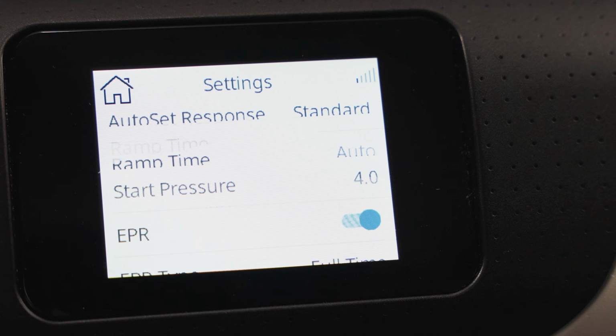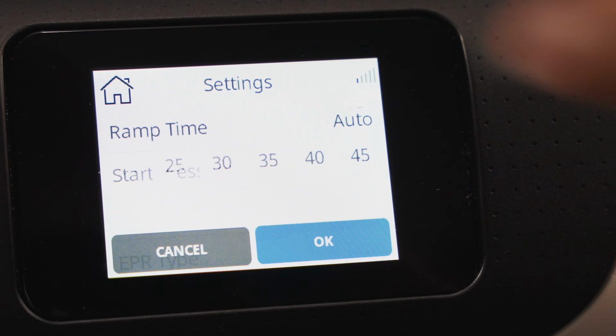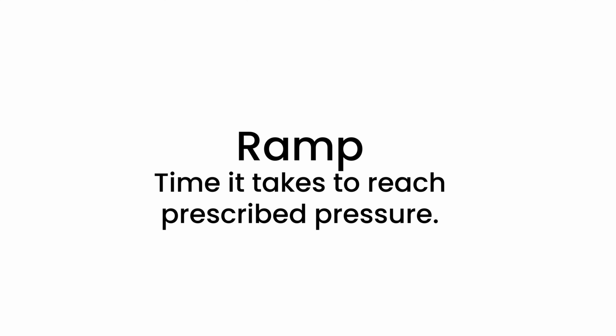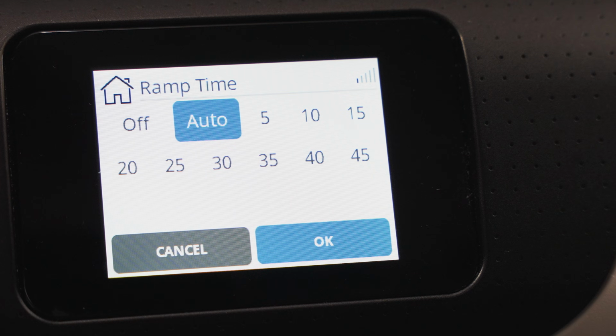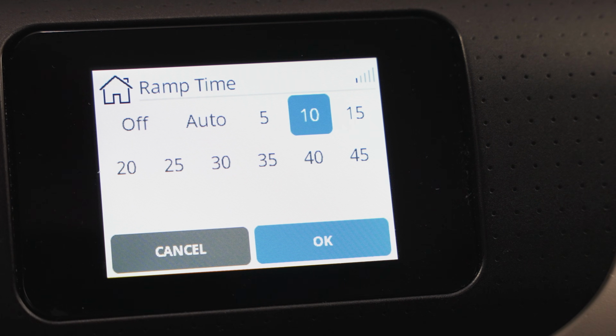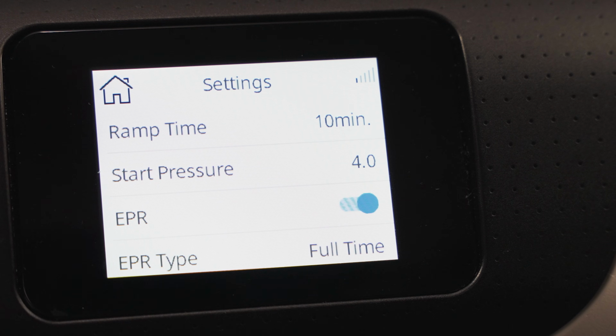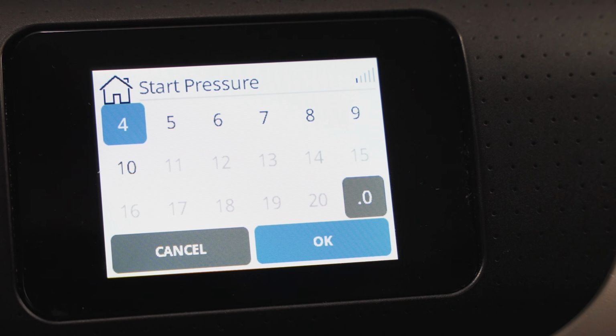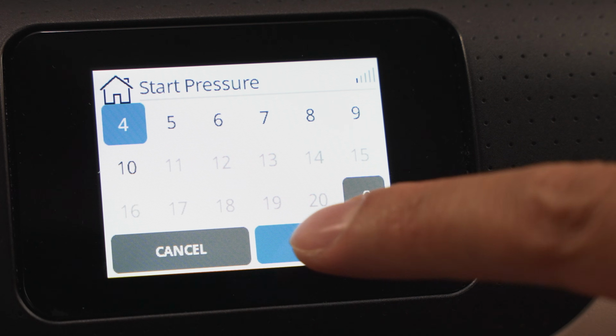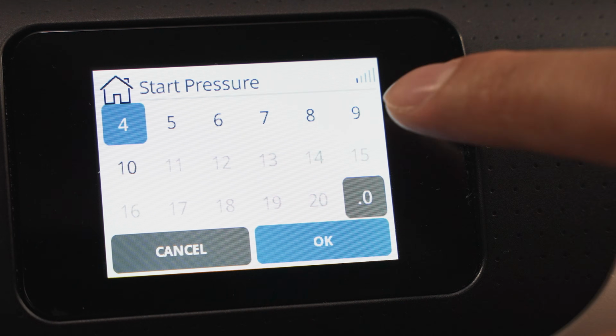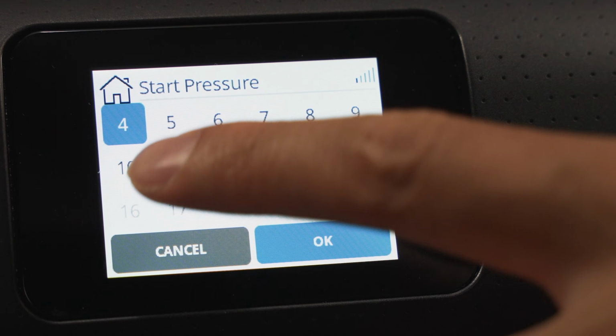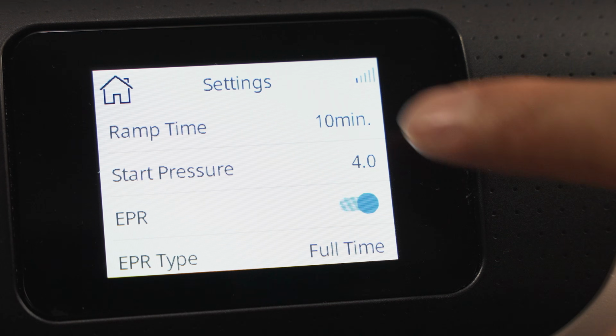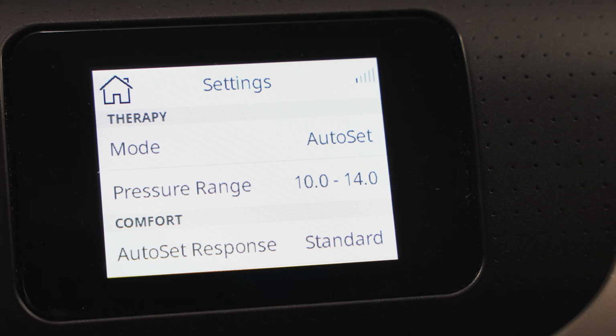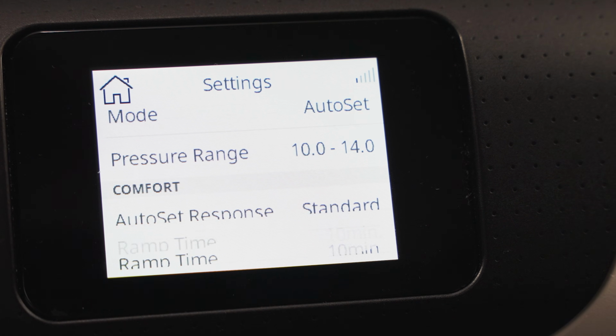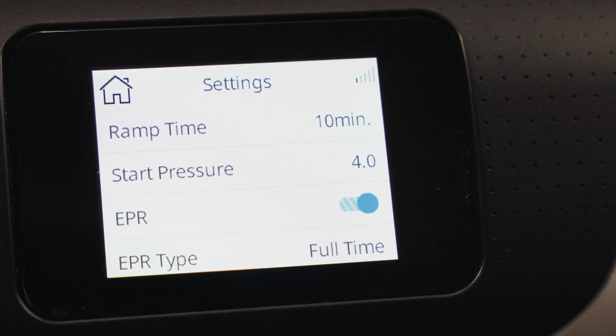Okay, moving on here, we have the ramp time. So that's gonna be the amount of time it takes to get to your prescribed pressure. You can have that at auto, so when you fall asleep, it's gonna go to that pressure, but I'm just gonna put it at 10 minutes, for example, and click OK. Pretty simple. You have your starting pressure, so you might want to start at 4 because that's nice and low, so it's going to be super, super comfortable. And over that 10 minutes, it's going to go from 4 to a 10. The reason that 10's there is because, like I said, our prescribed pressure is 10 to 14. So it's taking 10 minutes to get to that pressure.